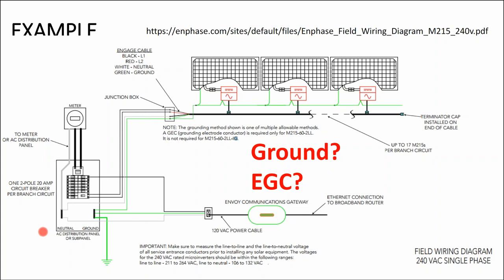It's the ground that connects all your metal pieces and then gets connected up to your ground bar. Now, there's your equipment ground conductor that's grounding the metal outlet box and keeping it at its low potential. And if the electricity in that outlet box should go wrong, it hits the side of that metal outlet box and that current travels down the metal equipment ground and goes into ground. And yeah, that can cause breakers to trip and ground fault detections to trigger, but that's how it's supposed to work. So we have the grounding electrode, the grounding electrode conductor, and then the smaller equipment ground conductors that route to it.